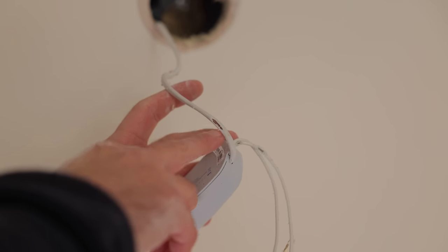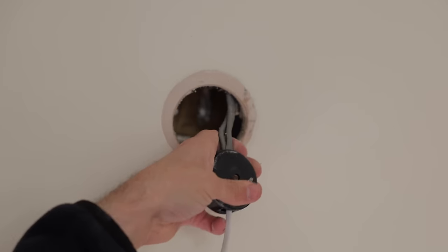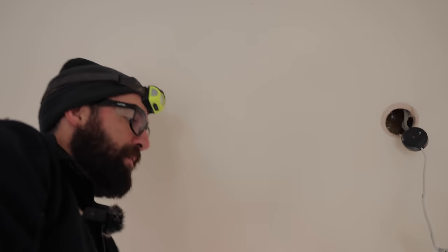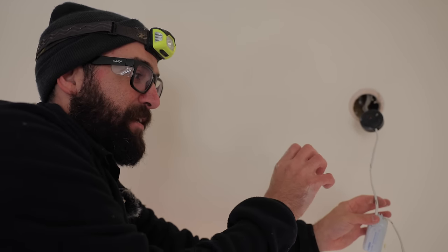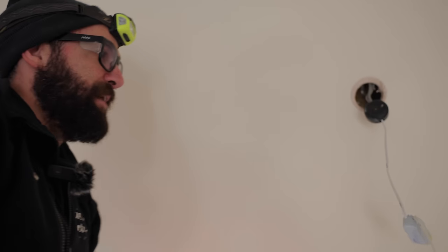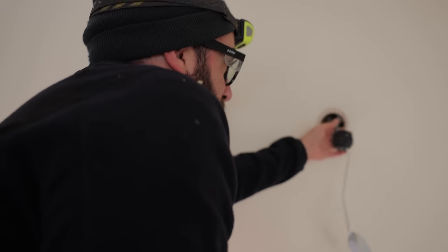So it's been eaten here, along there. The rodent damage is quite bad. I'm assuming squirrels because of the rural location, but it could be mice or rats, but I don't know how they get up this high. I suppose they can climb. I'm no animal expert, but apparently their teeth don't conduct electricity, so they can actually eat right up to the inner core of the cable without getting a zap. It's only when they go across live and earth, for example, that they get zapped.